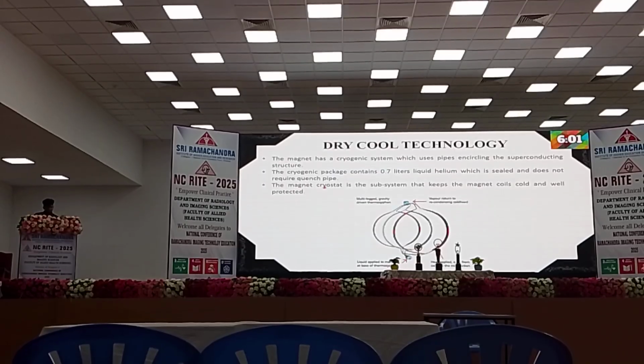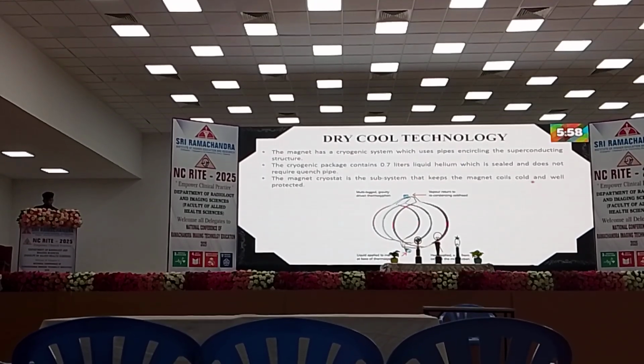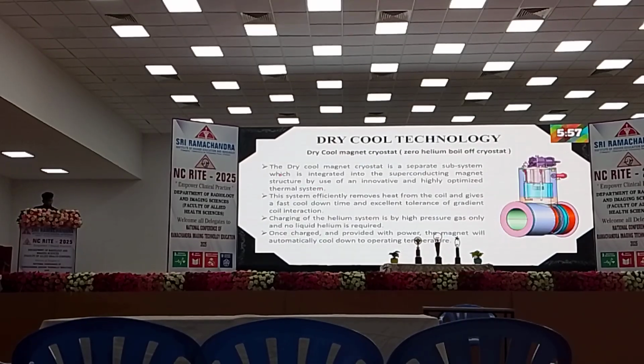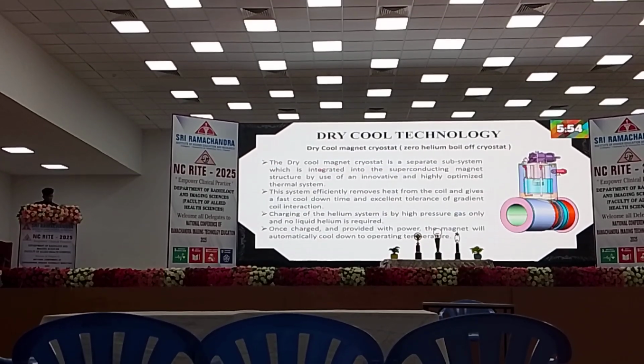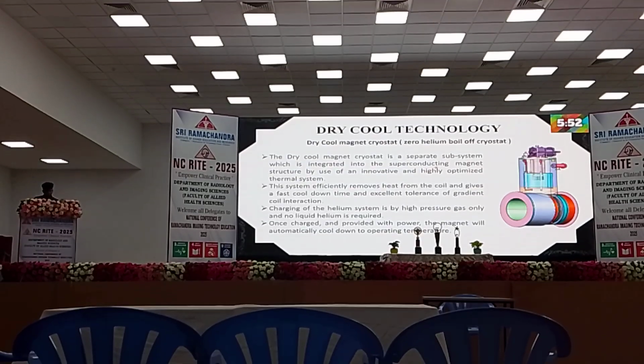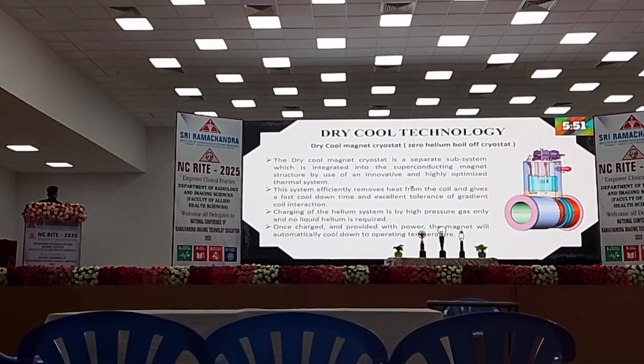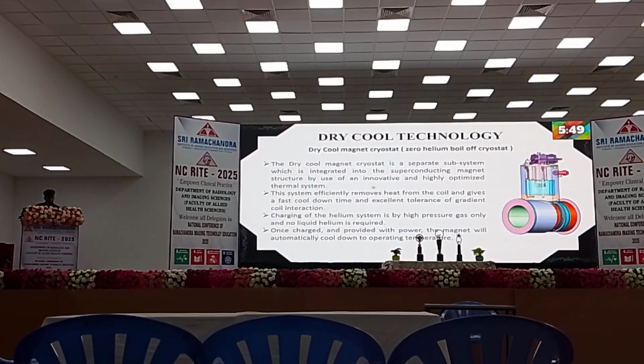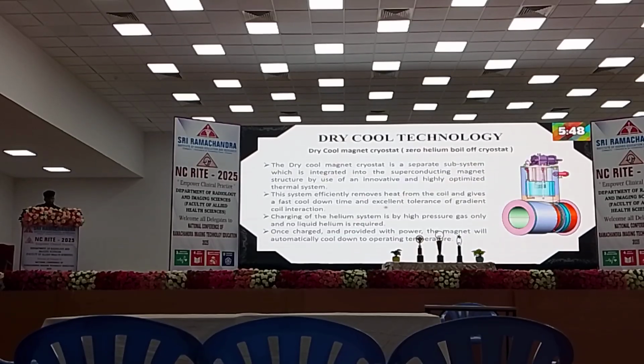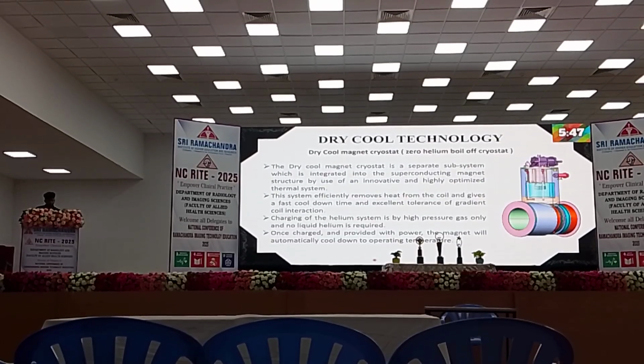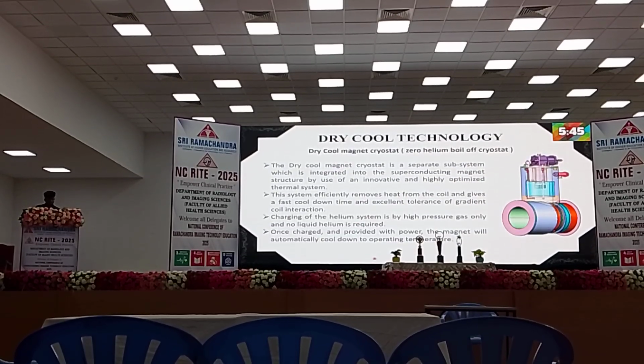The magnet cryostat is the subsystem that keeps the magnet coil cold and well protected. The Dry Cool magnet cryostat is a separate subsystem which is integrated into the superconducting magnet by a highly optimized thermal system to efficiently remove heat and automatically cool down to operating temperature, with the helium system charged by high pressure gas.